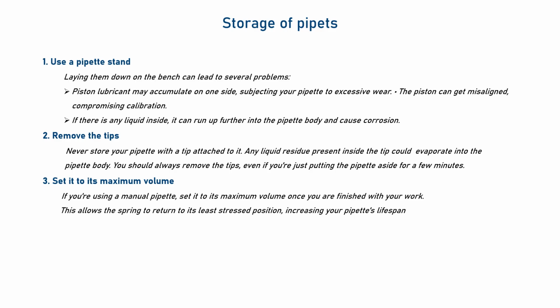The third point is to always set the pipette to the maximum volume when we are storing it. Inside of the pipette there is a spring, and we don't want it to be stressed all the time. So set your pipette to the maximum volume to release any stress on the spring, thus increasing your pipette's lifespan.